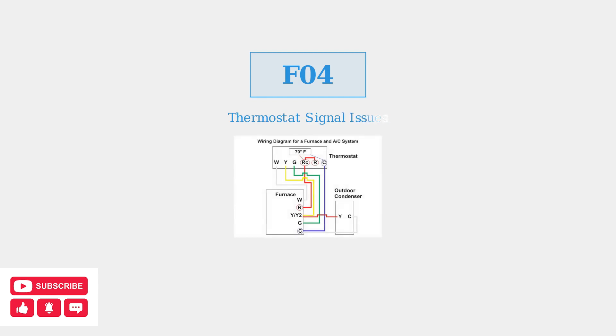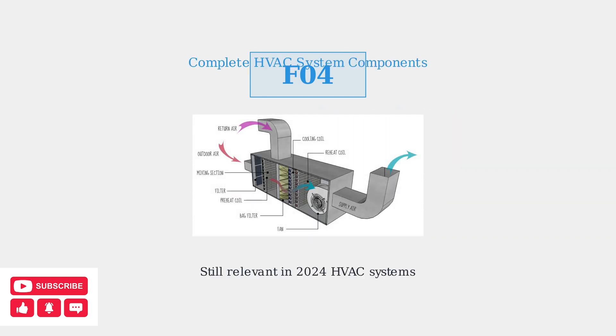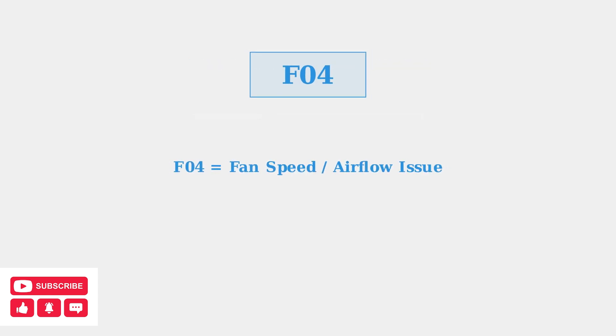The error typically means your system isn't receiving the correct signals from the thermostat, or there's a problem with the fan itself. Common causes include airflow problems such as dirty air filters, closed vents, or blocked evaporator coils that can cause the system to overheat. The problem might also originate from the outdoor unit, making this error code still relevant for Goodman HVAC systems as of 2024. Understanding the F04 error code is the first step in diagnosing and resolving fan speed and airflow issues in your Goodman HVAC system.